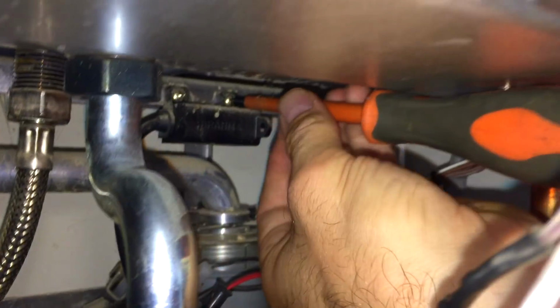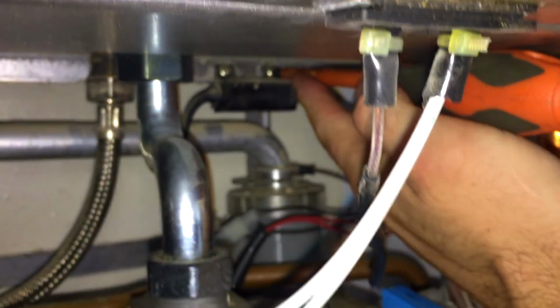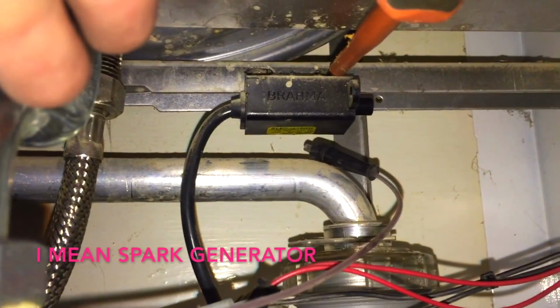Now I'm removing that igniter, as they call it. I would call it a transformer, but the manufacturer calls it an igniter. So I'm going to remove that, which is that plug there onto the board. While I've got it out, I'll do a comparison to the brand new one that's sitting there and see if there's any difference in the readings.